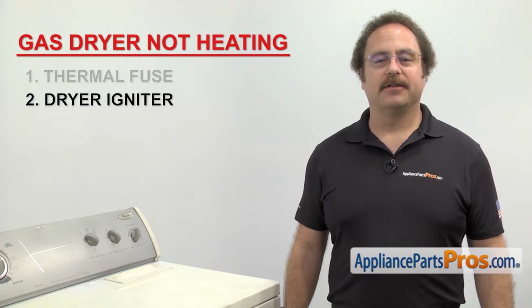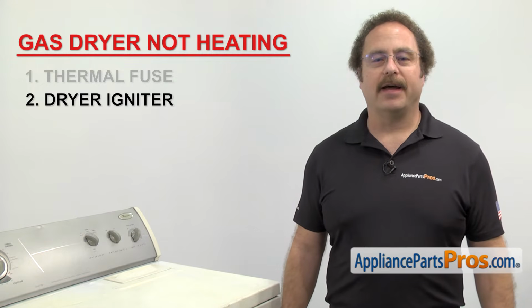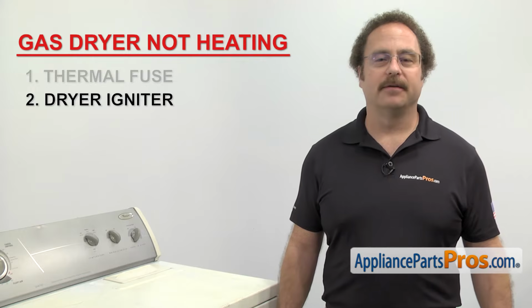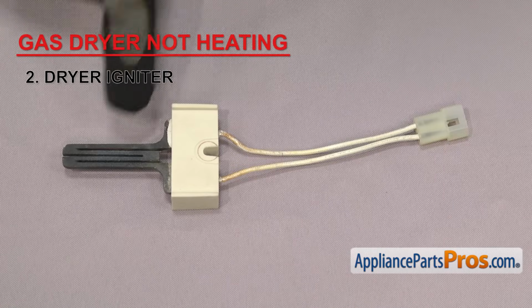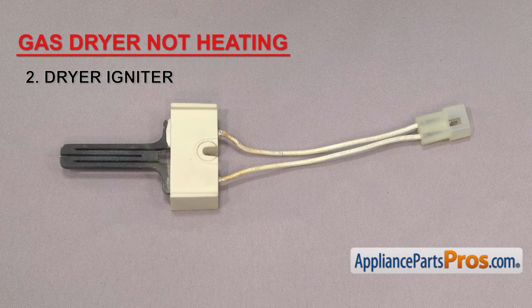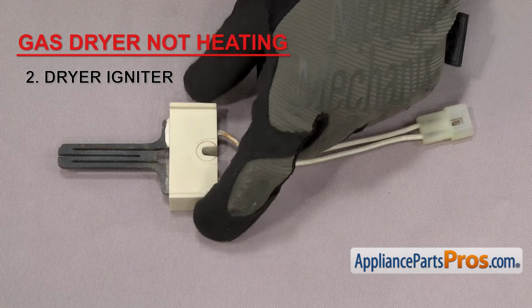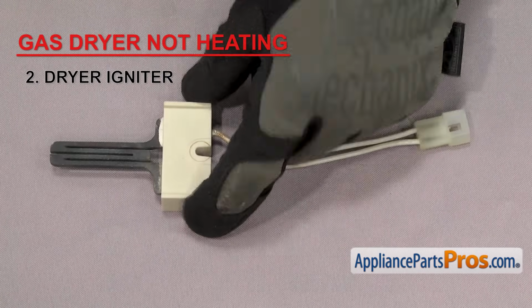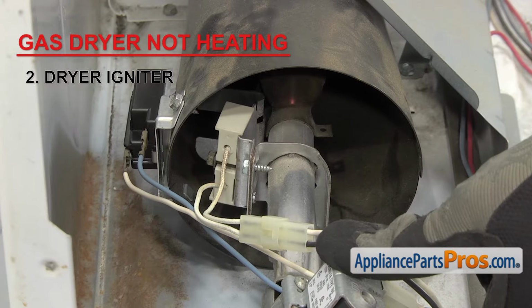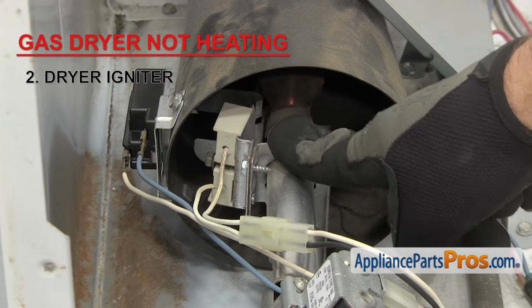Next, we have to check the dryer igniter. The dryer igniter glows red hot to ignite the gas to heat the dryer. It has a ceramic base with a gray heating element. The heating element is very fragile, so if you have to take it out or handle it, make sure you only do it by the base. The igniter is located by the burner assembly, usually mounted on the burner tube.